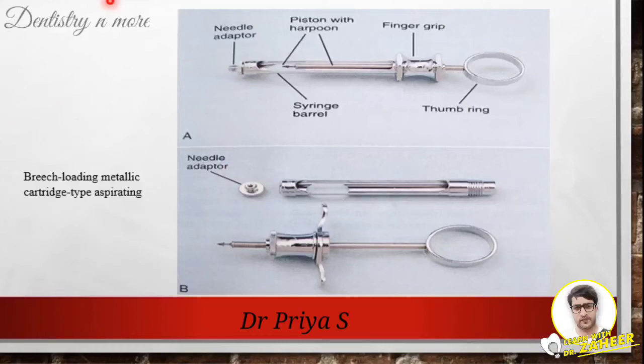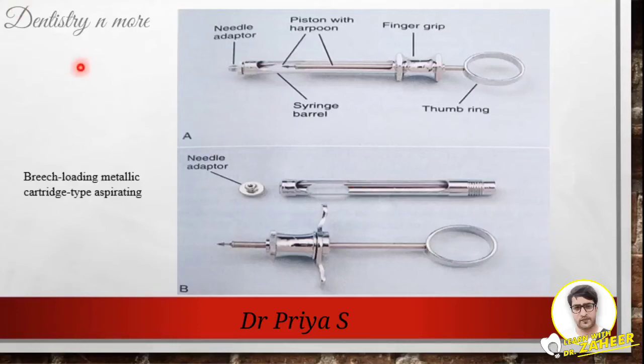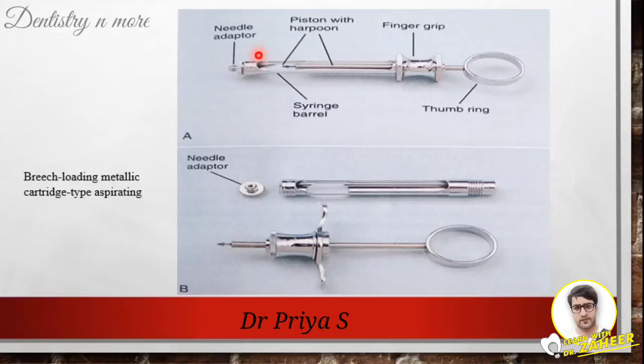The term breech-loading implies that the cartridge is inserted into the syringe from one side of the barrel. There is a hinge mechanism which is operated to insert the cartridge into the syringe barrel. The needle is attached to the barrel of the syringe at the needle adapter, and it passes into the barrel so that it penetrates the diaphragm of the local anesthetic cartridge, which is inserted into the barrel prior to insertion of the needle.